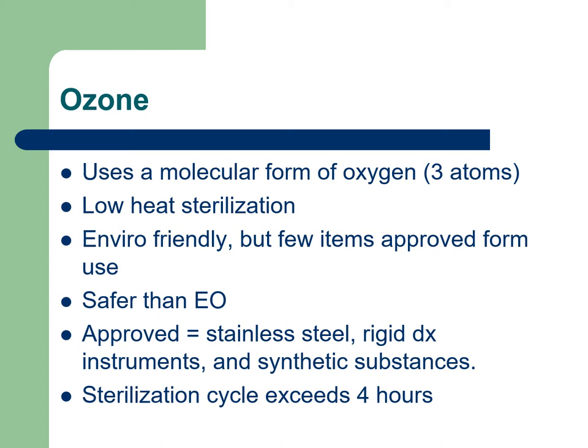However, it hasn't been approved for a lot of items. Some items it has been approved for include stainless steel, rigid diagnostic instruments like endoscopes, and some synthetic substances like those made out of PVC, silicone, or PTFE—which includes grafts and meshes made of those materials. It is not approved for implants, and it takes 4 hours plus for the sterilization cycle, so it's not a fast fix if you need something right away.